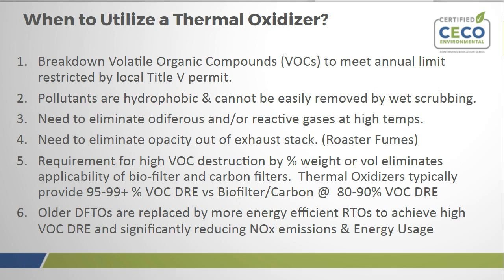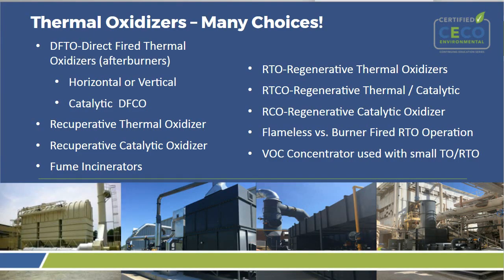There's many choices of thermal oxidizers. As I mentioned, we have the direct fired, also called afterburners. You can get these in a horizontal or vertical fired type arrangement. There's the recuperative thermal oxidizer that would typically use a shell and tube or plate and frame type heat exchanger to recuperate and reduce energy. Typically, those are about 35 to 80% thermal efficiencies. The RTO thermal oxidizers, those are between 90 to 97% thermal efficiency. We see that as being one of the more flexible technologies. You can also have an RTCO option, where you can have the RTO operating with a catalyst bed at the top at lower temperatures, and we see that a lot in the wood industry.